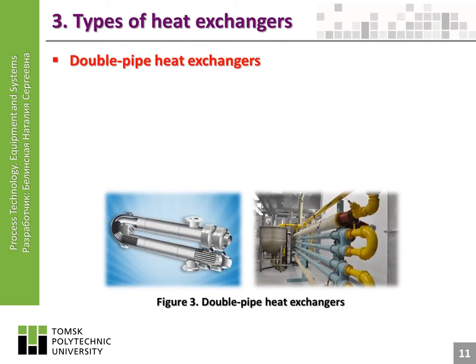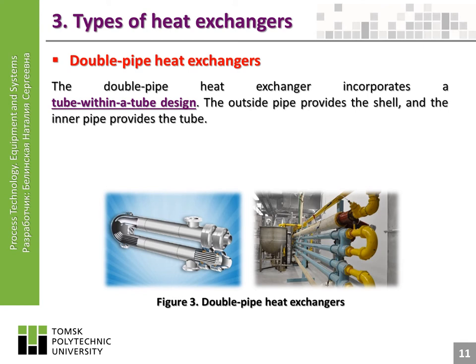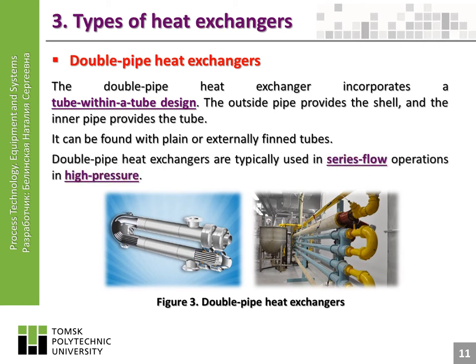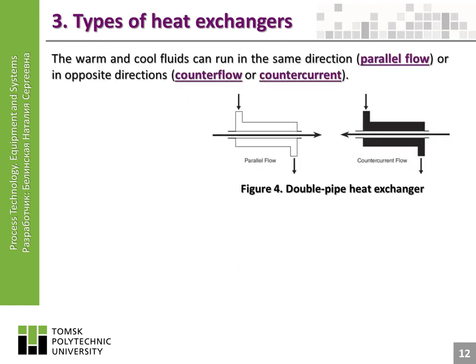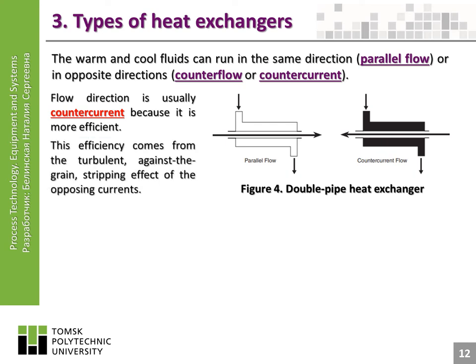Double pipe heat exchangers. The double pipe heat exchanger incorporates a tube-within-a-tube design. The outside pipe provides the shell, and the inner pipe provides the tube. It can be found with plain or externally finned tubes. Double pipe heat exchangers are typically used in series flow operations at high pressure. The warm and cool fluids can run in the same direction (parallel flow) or in opposite directions (counterflow or countercurrent). Flow direction is usually countercurrent because it is more efficient, due to the turbulent, against-the-grain stripping effect of the opposing currents.